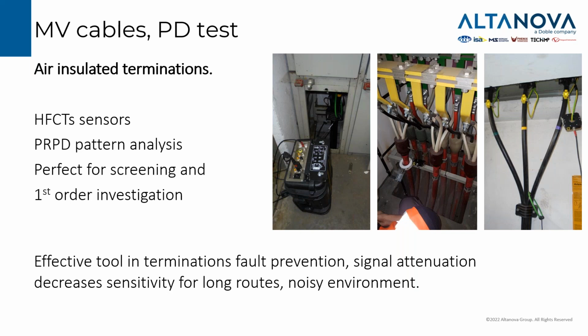We can have some issues because of the noisy environment, and we have to consider that there is an attenuation of the signal for long cables. So if we are testing a 10 kilometer cable and there is a small PD event in the middle, by testing the terminations only, it is possible that such a signal doesn't reach the terminations. So it's something that we have to take into account.